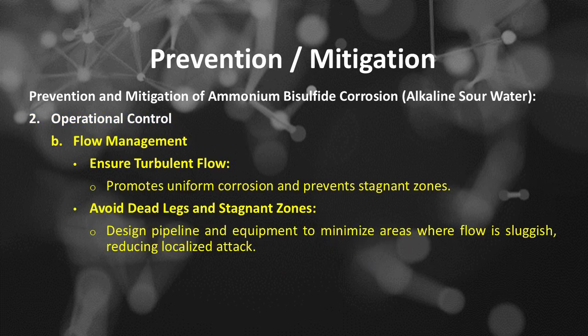Operational control, number B, is flow management. Ensure turbulent flow, which promotes uniform corrosion and prevents stagnant zones. Avoid dead legs and stagnant zones, and design pipeline and equipment to minimize areas where flow is sluggish, reducing localized attack.